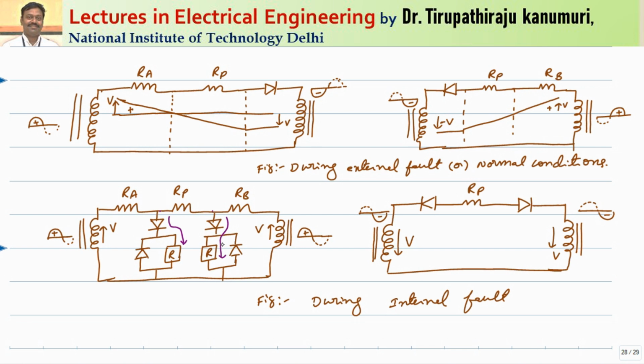So let us assume it is a single fed system. If it is a singly fed system, automatically the second side voltage is nearly equal to 0 or very less. In that case, only this relay will operate, because this will be forward biased and this will not be forward biased. Getting this one? In this way they will operate.